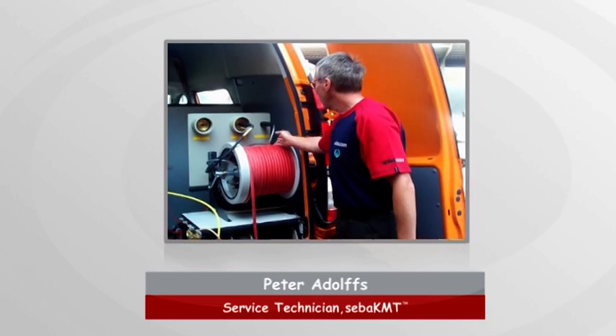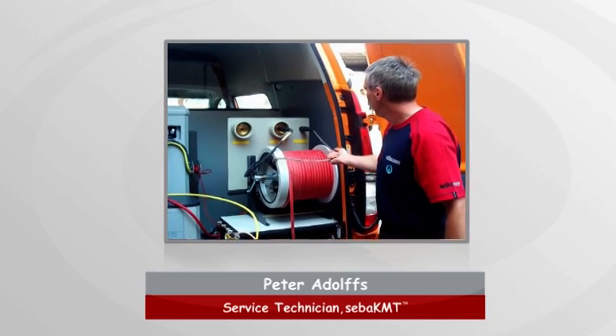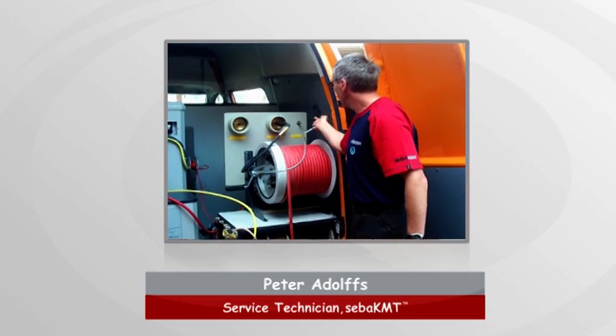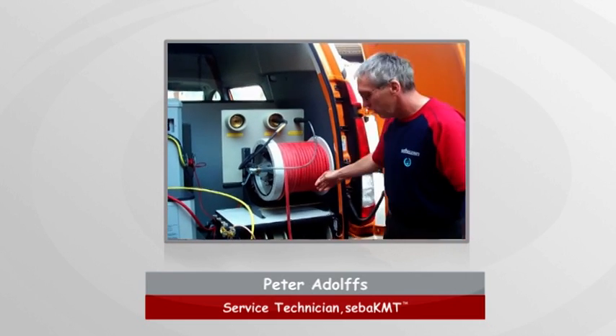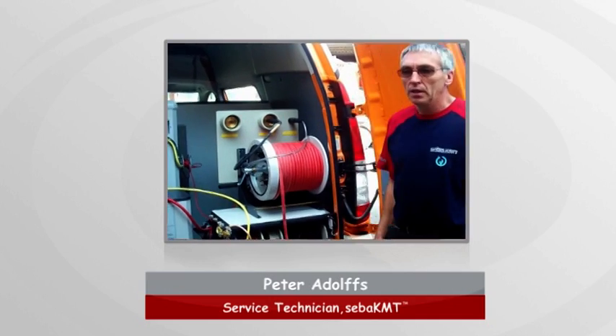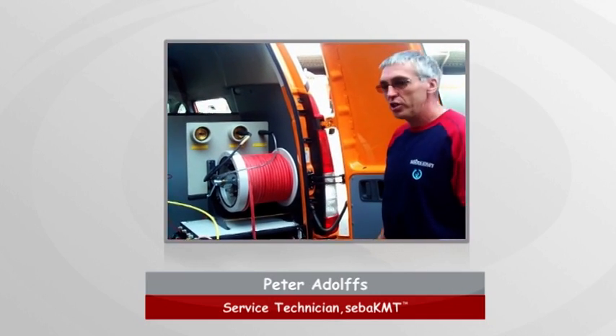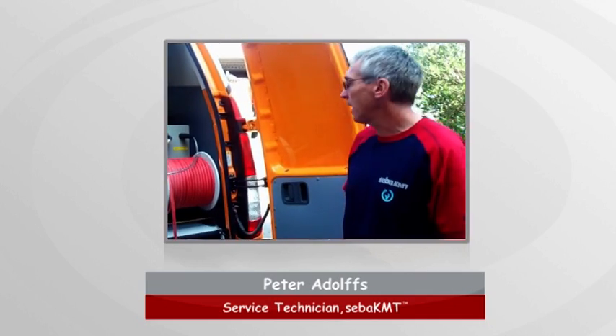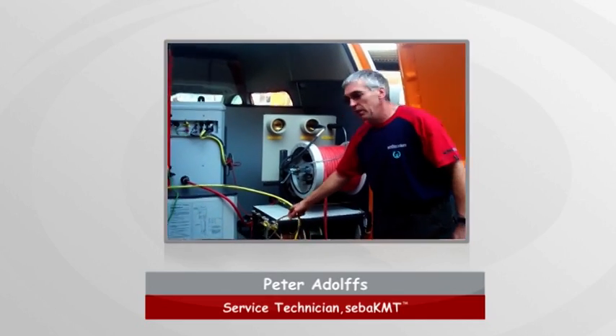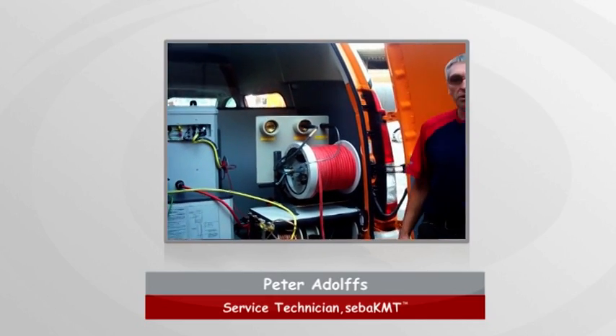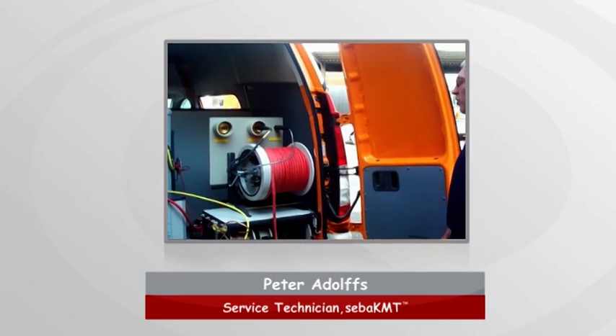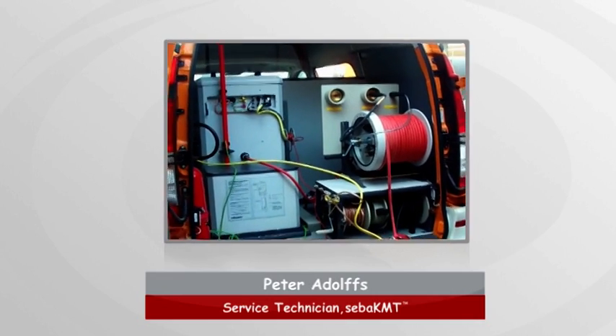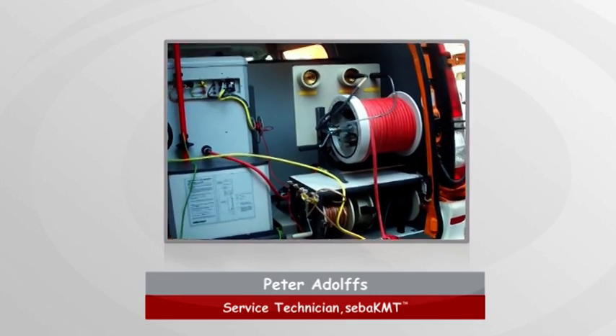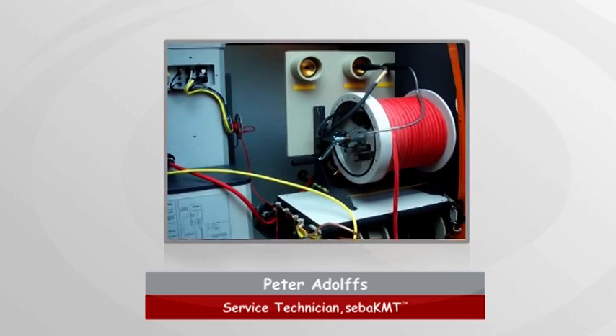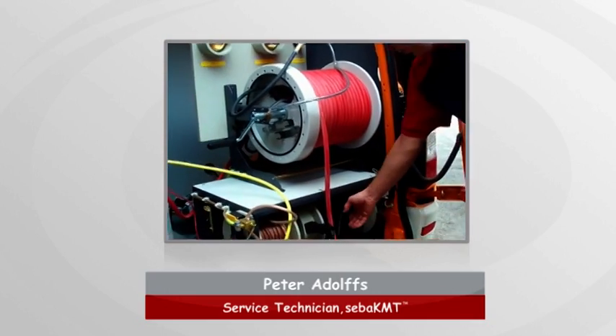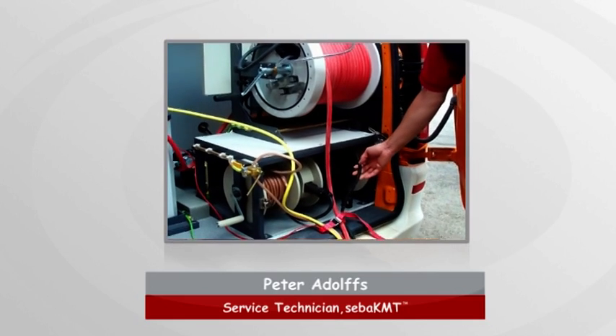We also have an operational earth here. We have to connect the ground here. This is a ground from our high voltage substation. It should be the same potential as our protection ground. If there is any difference between the potential systems, the system cannot be switched on if the resistance is higher than 12 ohms.